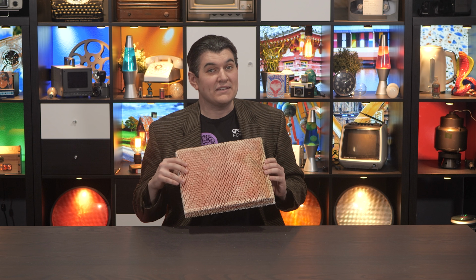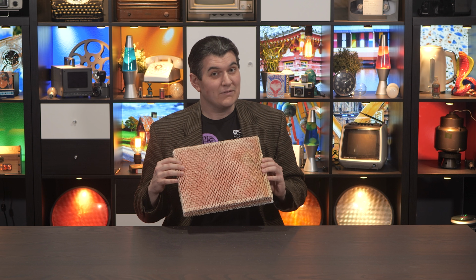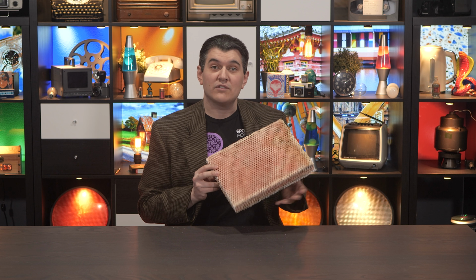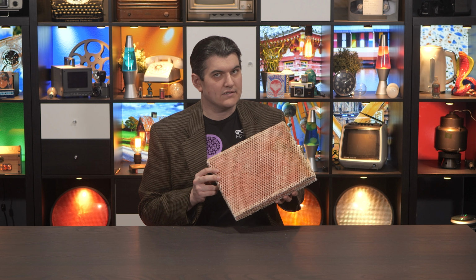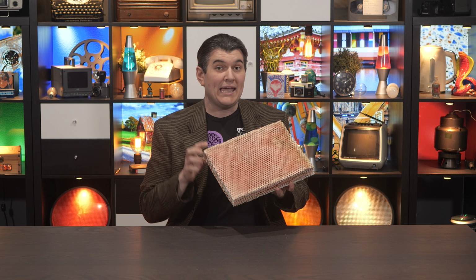Remember that thing I said about these needing much more attention than you might expect? Well, one day I heard the water valve open, but I didn't hear the fan start up. And that was because the pad had started to deteriorate, and part of it fell forward and into the fan blades, holding them stationary.